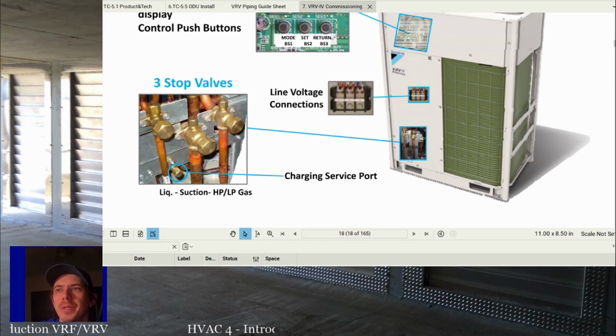If you're familiar with critical systems like Liebert systems and something like that with semi-hermetics, sometimes you end up adding oil because of the amount of oil that has to circulate through the refrigerant system. All oil ends up circulating through the refrigerant system somewhat. So if it's a long piping run, sometimes you have to add oil to make sure that you maintain a proper oil level in the compressor. And in these systems, you don't add oil to maintain that oil level. So the oil that's in there is all you get to maintain the proper oil level in all 6 of those compressors in our example.